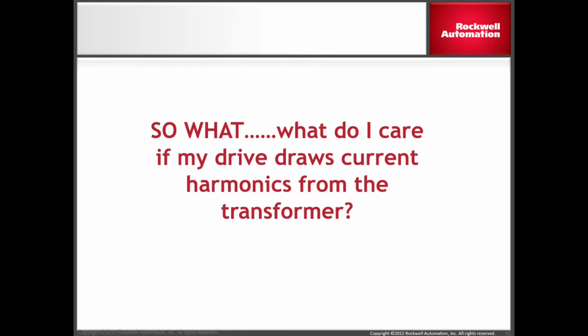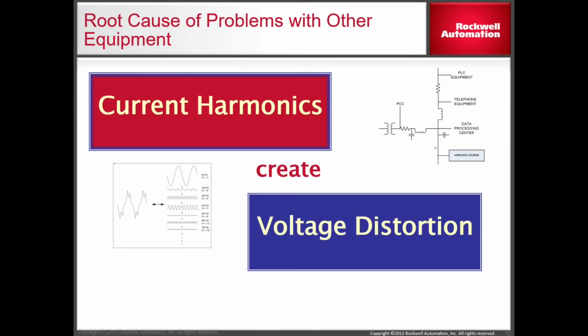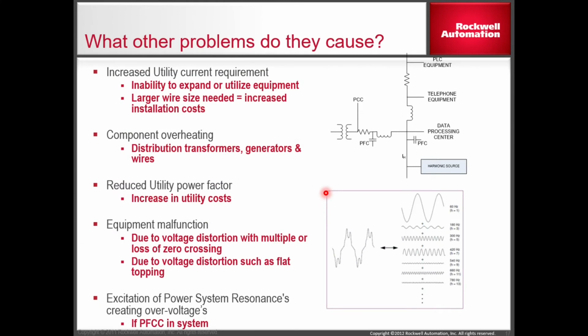So what's the big deal? What do I care about that? Well, the more harmonic currents you produce, the bigger the voltage distortions in your plant, and that could lead to a lot of other issues. One of them being component overheating of transformers, generators, wires, even motors. And even though we put drives in there for pumps and fans to reduce utility costs, we're sometimes reducing the power factor as well in our plant, which is counterintuitive. We're adding drives to reduce energy, but the power factor may be getting a little worse, so we're causing us to consume more energy. But you'll save more than you consume. So that's why people add drives, for cost savings.